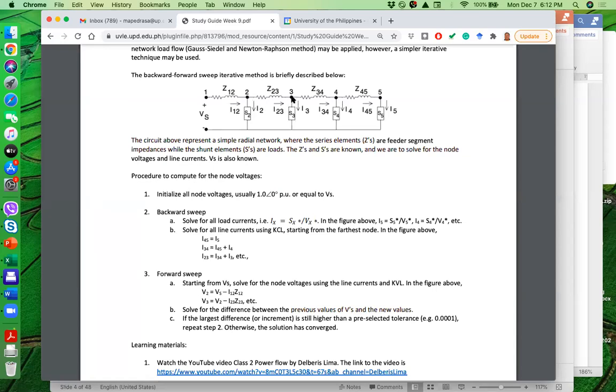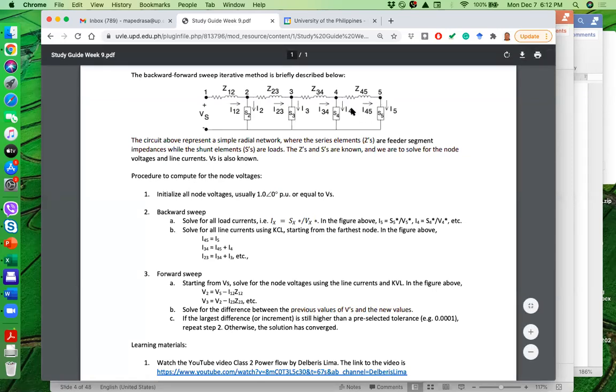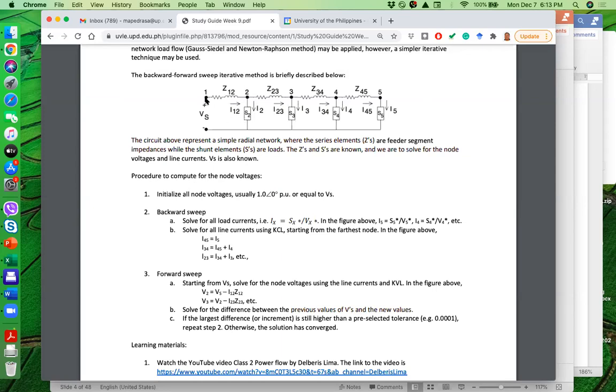Once we have V2, we solve for V3 using KVL: V3 equals V2 minus Z23 times I23. Then V4 equals V3 minus I34 times Z34. Then V5 equals V4 minus Z45 times I45. After that forward sweep, we have new values for the load voltages. Using those new voltages, we recompute I2, I3, I4, I5, and solve for currents again using KCL.